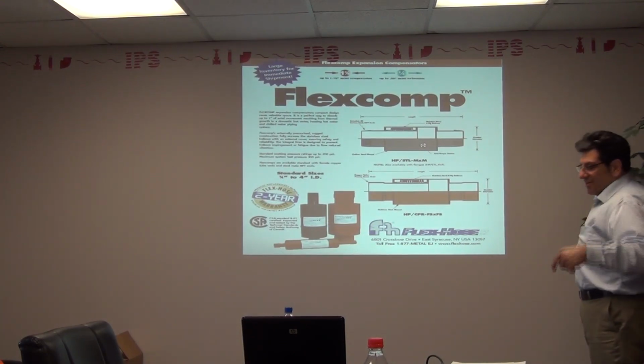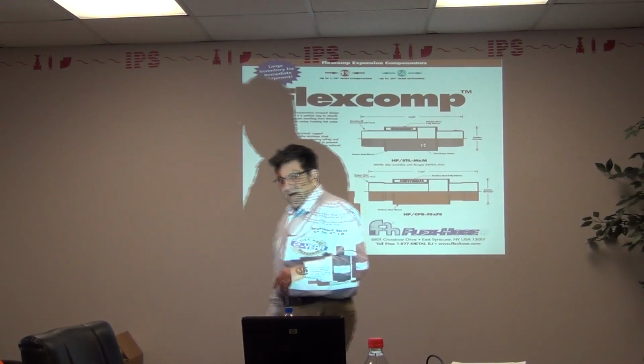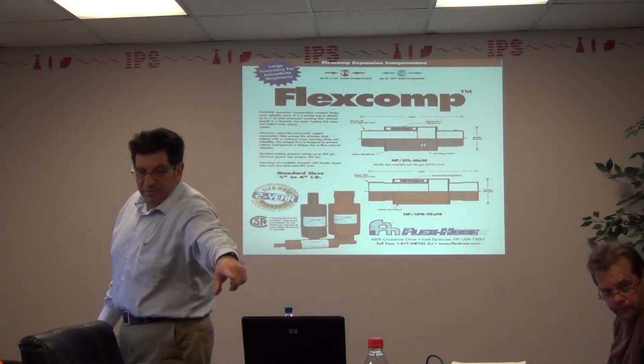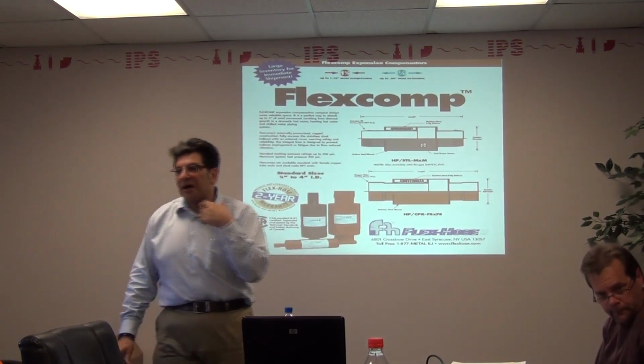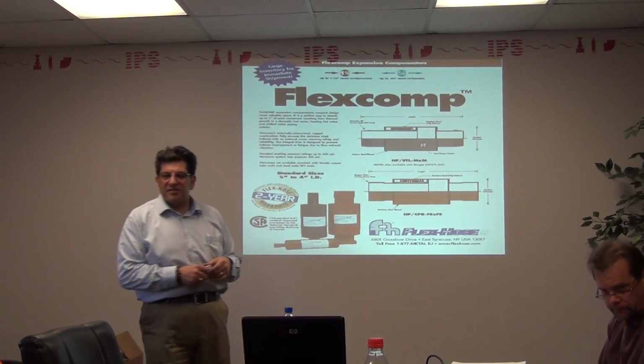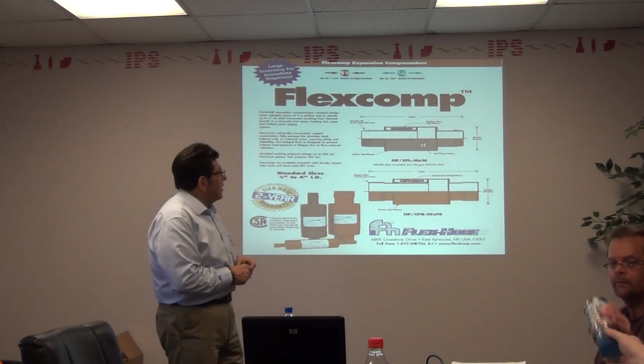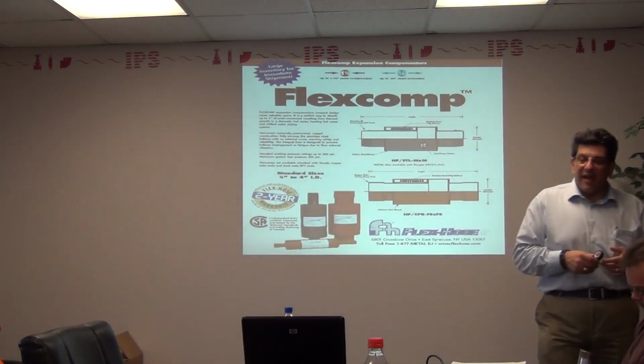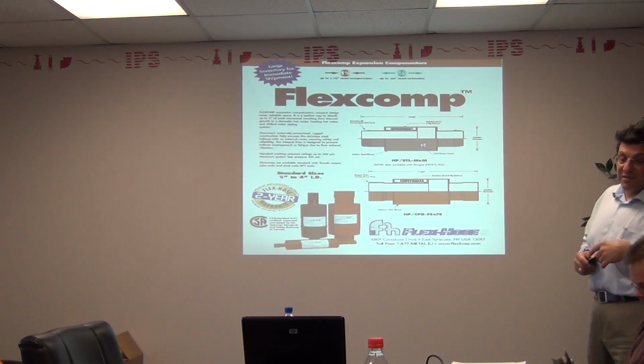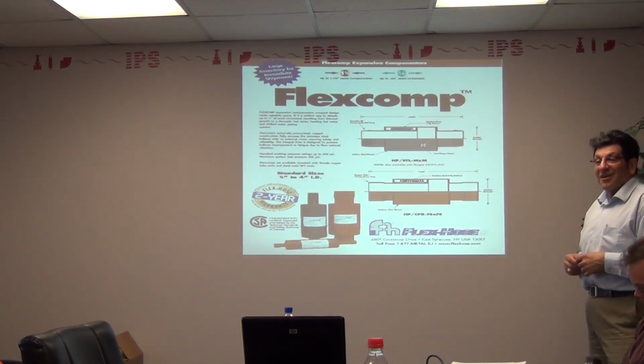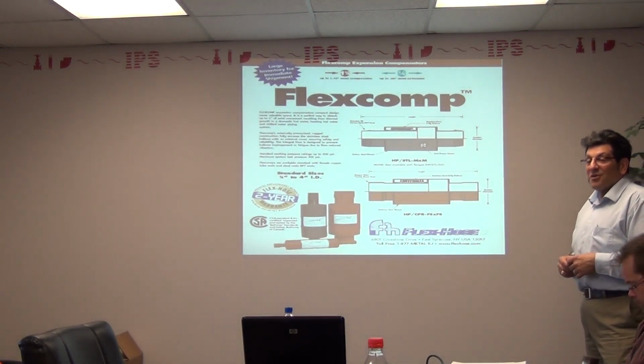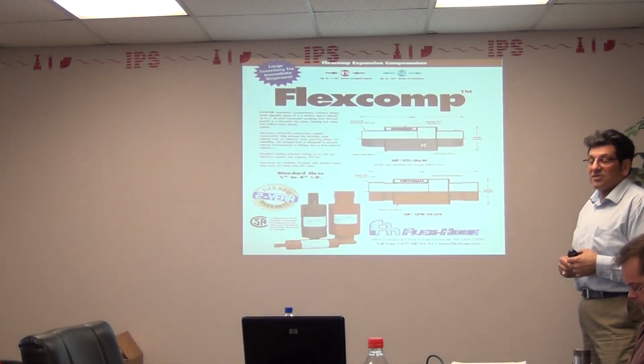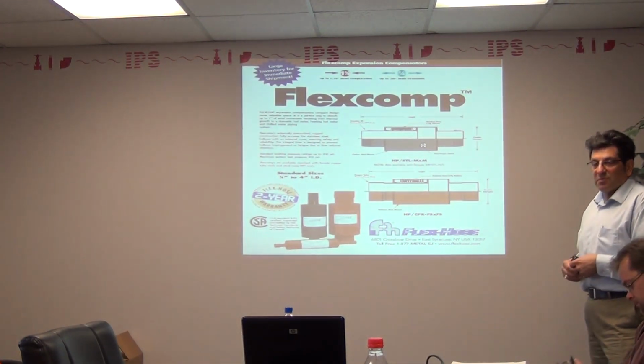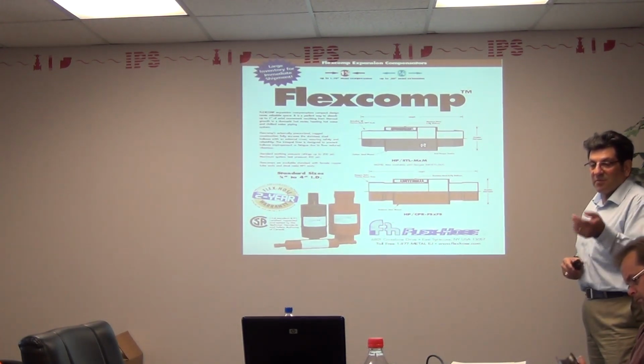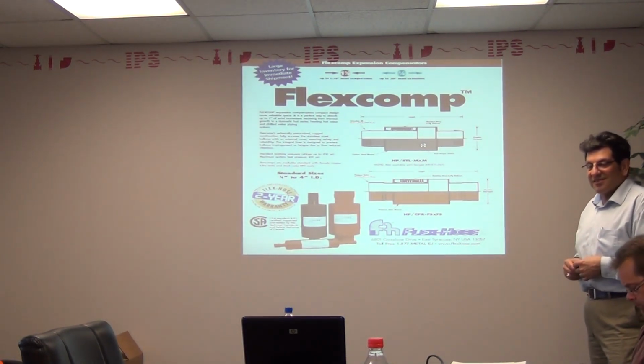Flex comps - you see a lot of these, and I'm going to tell you right now, 80% of these are installed improperly. People will put them in - they're usually used on larger HVAC systems or smaller water systems, you'll see them on domestic systems. They're never guided or anchored properly. There's a guide built into that, but folks just don't do it, and they fail at record rates. You go to larger cities or really vertical places, you'll see service people or maintenance facilities people keep a couple dozen of these on the shelf.